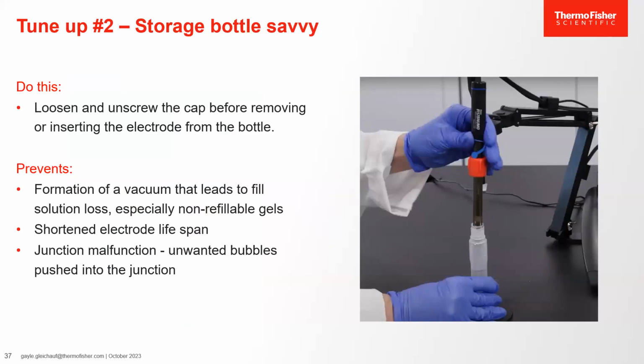Tune-up number 2, storage bottle savvy. Remember to loosen and unscrew the cap from the bottle before removing or inserting the electrode. When removing the electrode, prevent an unwanted vacuum that can pull fill solution out of the electrode and shorten the electrode use life. When returning the electrode to the bottle, prevent unwanted bubbles being pushed into the junction that can stop it from working properly.